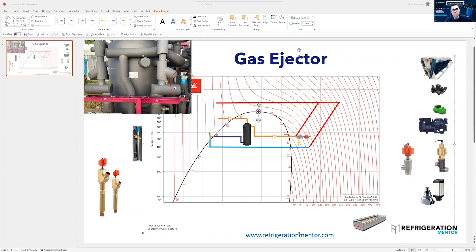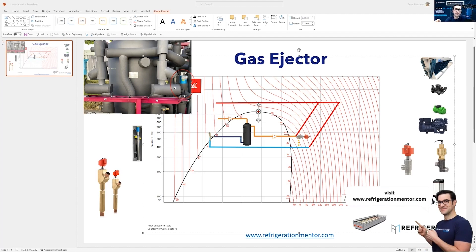What the ejector is doing, once again, is taking the gas coming from the suction line evaporators, the medium temp suction line evaporators, and putting it into the flash tank. Then the flash tank is putting it through the parallel compressor instead of going into the medium temp compressors.